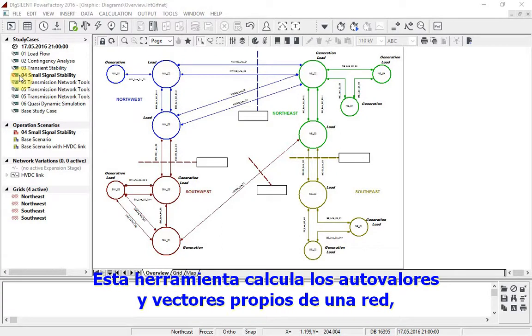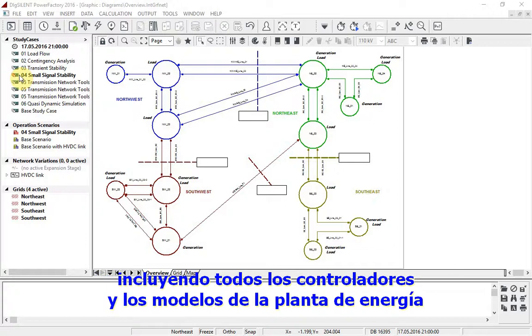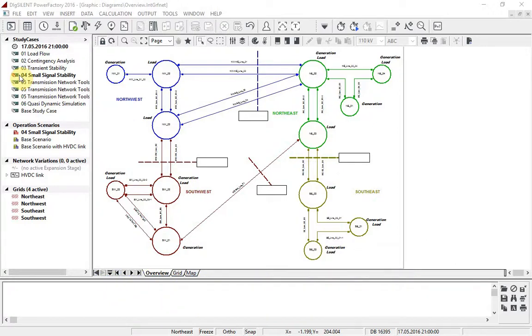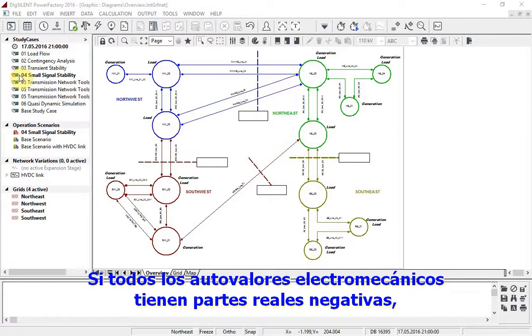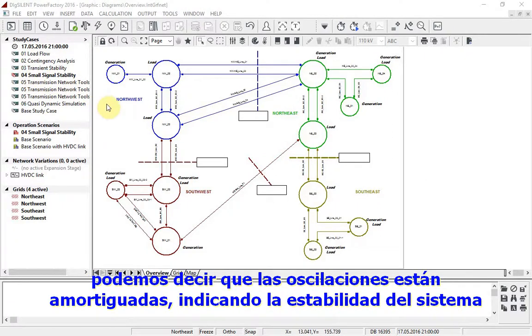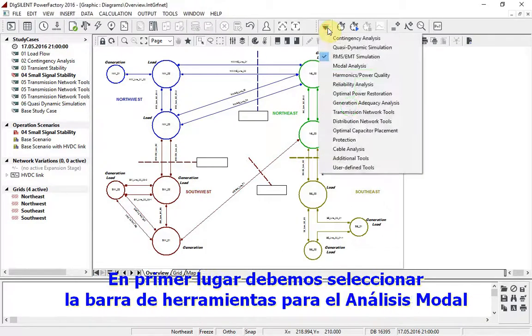This calculates the eigenvalues and eigenvectors of a network, including all controllers and power plant models. If all the electromechanical eigenvalues have negative real parts, we can say that the oscillations are damped, indicating system stability.